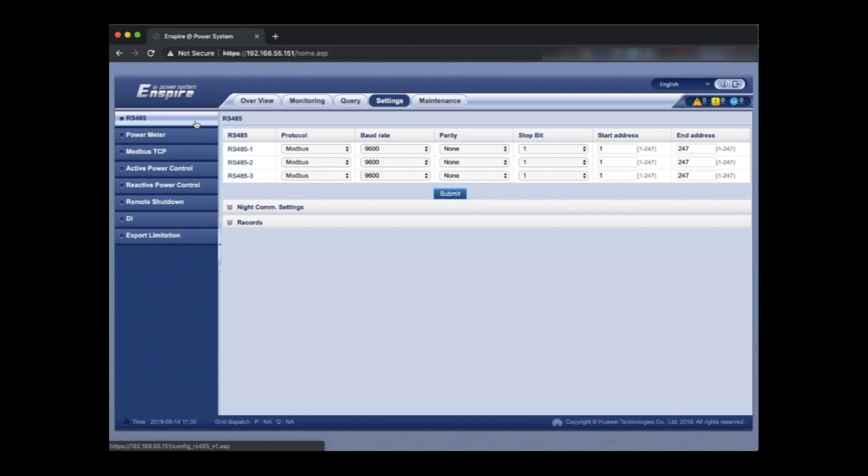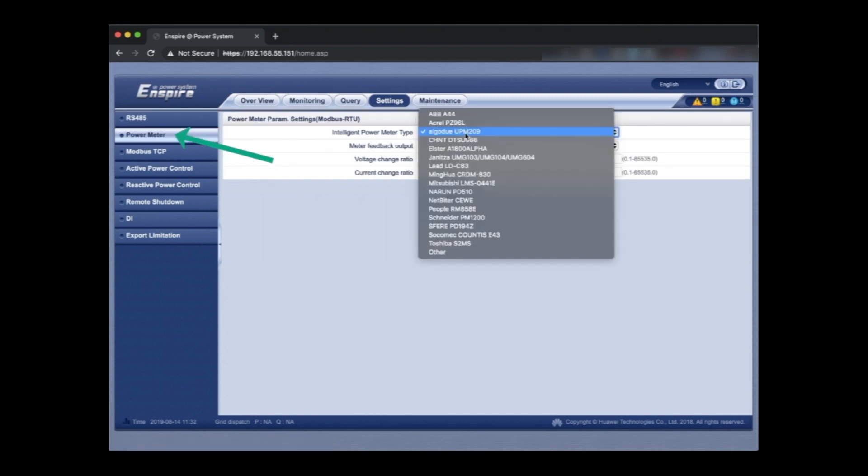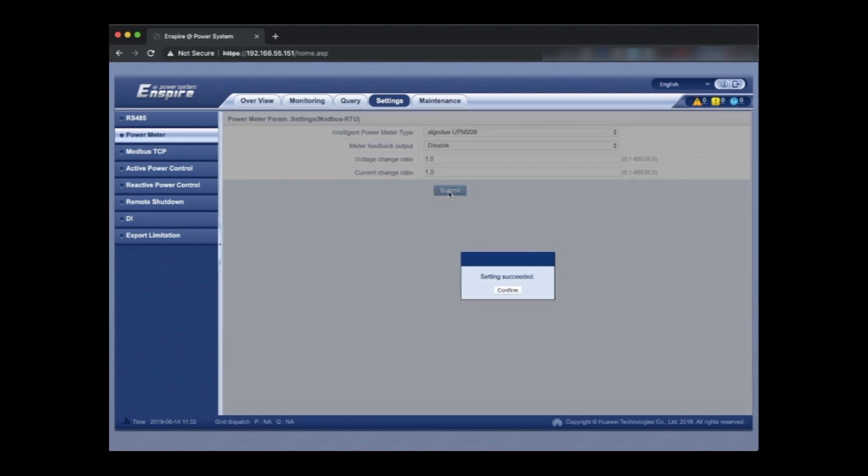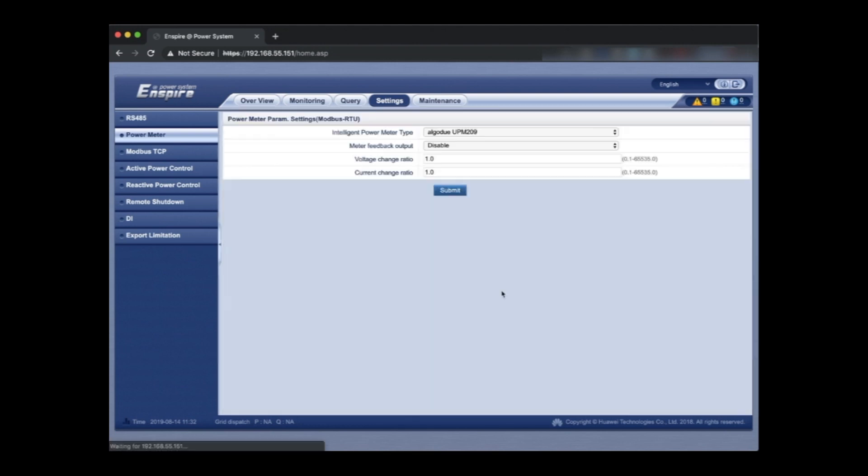So we're going to, if you're using any other meter make sure you select it from the drop-down list. There's quite an extensive list of meters but we're just going to use the Algodue as our meter for this application. Here you can see the list of meters, the Algodue UPM209 is the meter we're using. We don't need to change anything unless you're using a current transformer which may have ratios that you need to apply. But if you're using whole of current you can just leave those as one.